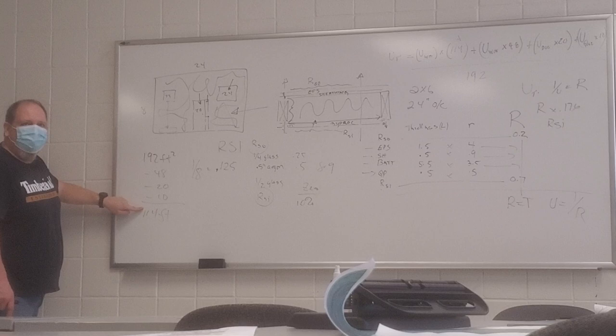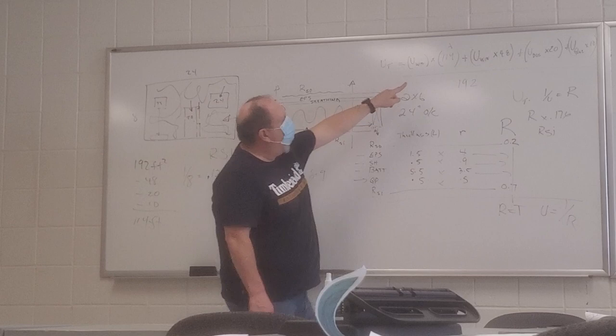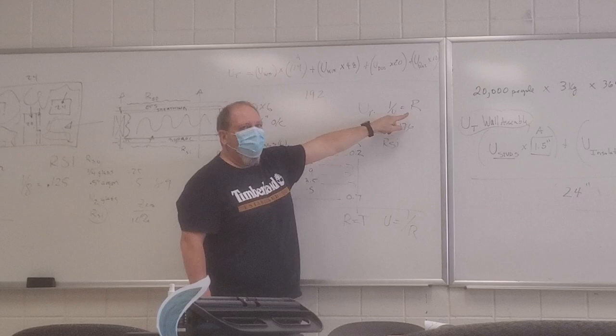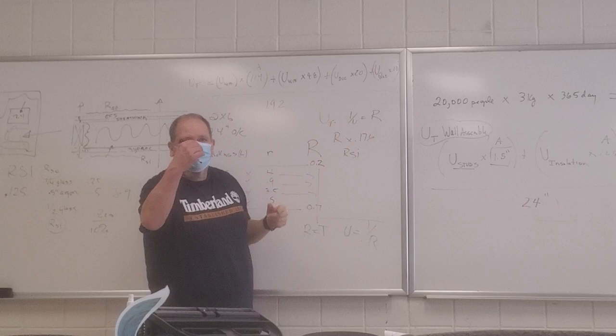So now we're left with 114 square feet. That's the weighted average. Divide that by the entire wall. You get a U-t. We come up with the R-value, right? And then R times 0.176 at the bottom of the chart gives us the metric conversion for it.